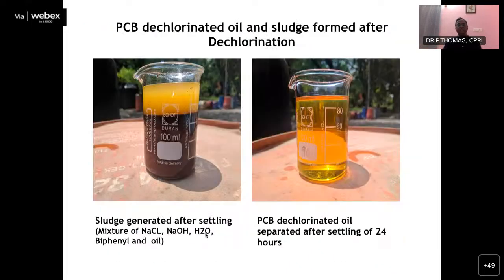You can see here, the PCB dechlorinated oil, once it is in the settling tank, will look like this. When you take the oil and immediately put it in a beaker, overnight it settles down like this. The same thing happens in the settling tank, which is designed as a cone type so the sludge easily comes down to the bottom and can be slowly removed.